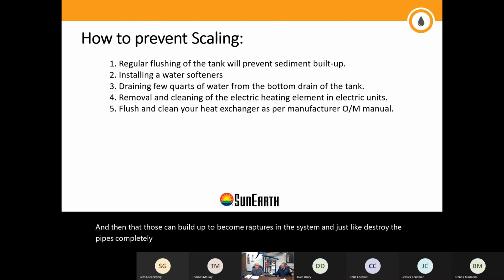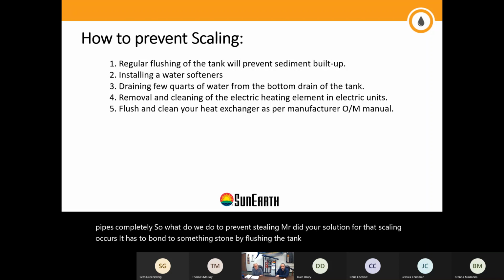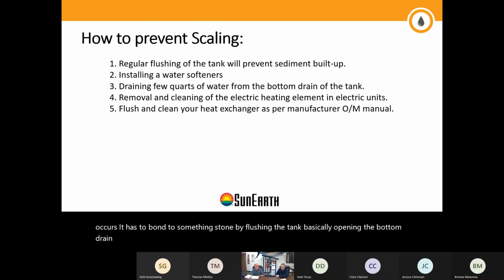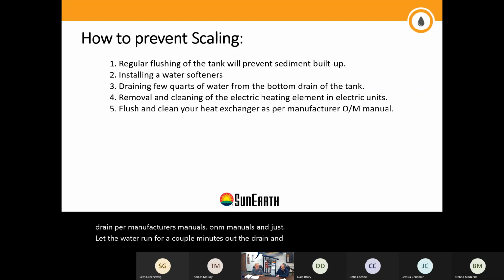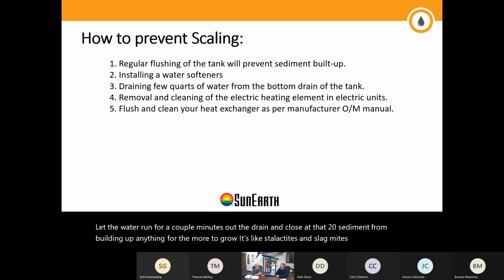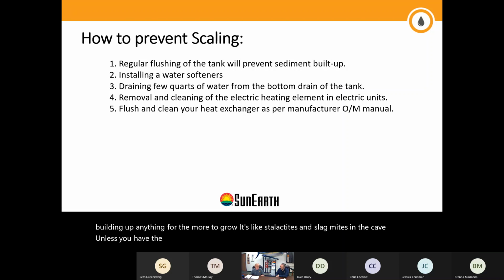So what do we do to prevent scaling, Mr. Danielson? What is your solution for that? Well, scaling occurs, it has to bond to something. So by flushing the tank, basically opening the bottom drain, per manufacturer's manuals, O&M manuals, you just let the water run for a couple minutes out the drain and close it. That keeps any sediment from building up, anything for the more to grow. It's like stalactites and stalagmites in a cave. The less you have, the less growth you'll have.